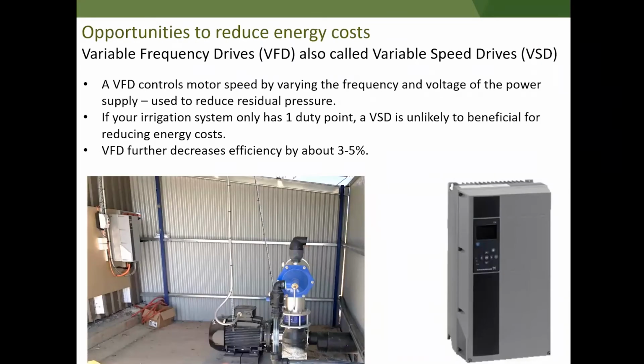So I'll just touch on variable speed drives now, also called variable frequency drives. For people who don't know what they are, they essentially control the speed of the motor. So this is a variable speed drive here. Without that, the motor runs at a constant speed. It can't be changed, so we can't change the flow rate and pressure on a particular irrigation system. So they're a really good way of managing that residual pressure, reducing the pressure at the end of the system, or making sure that the pump's running at the right revs for the system.